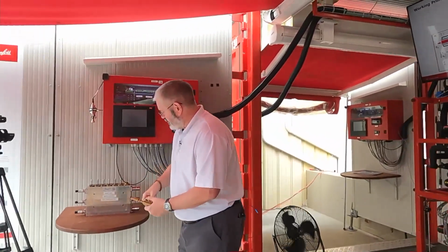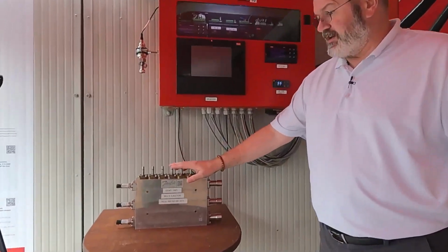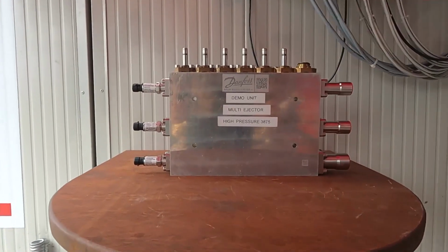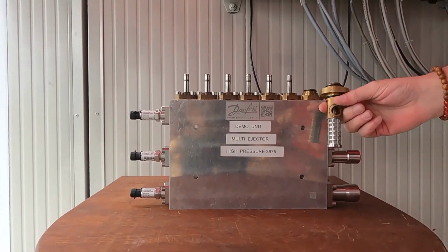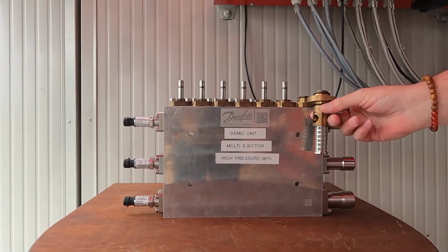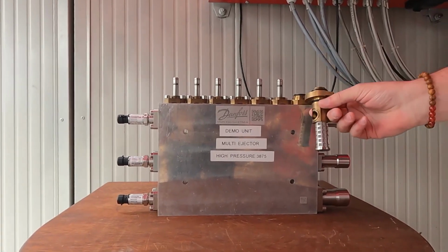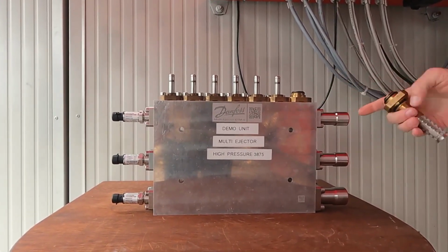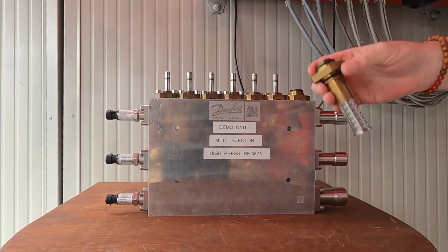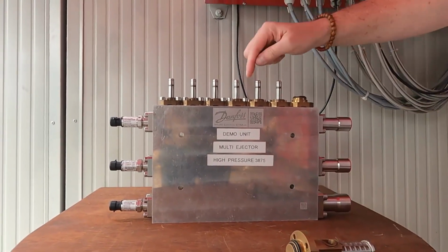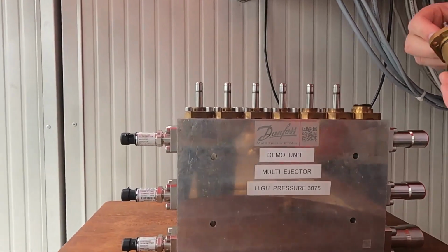So the ejector block looks like this. We had one on the other end; we showed it on the other end of the system earlier. This first piece is going to be our screen. It's a removable, serviceable filter screen, and all of the flow coming from the gas cooler will travel through this screen. And then here we have various ejector blocks, which is why it's called the multi-block.